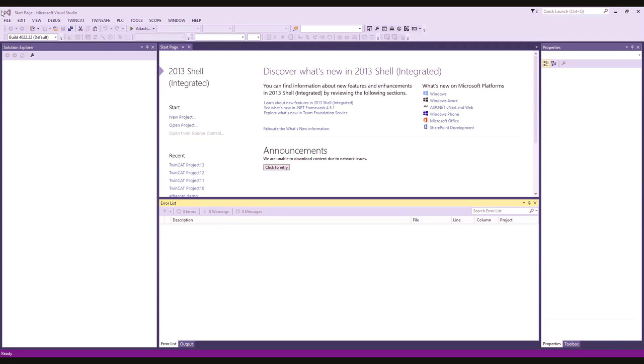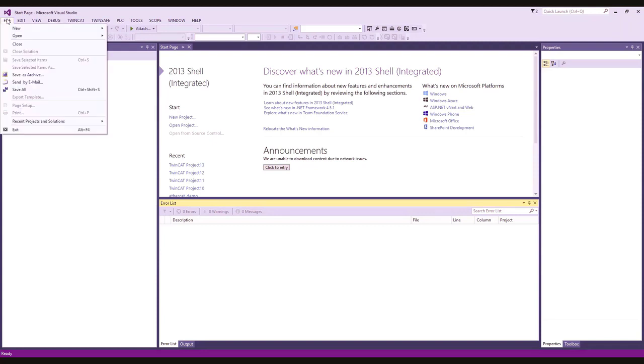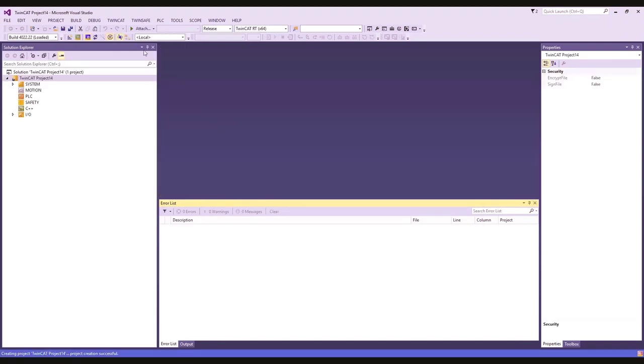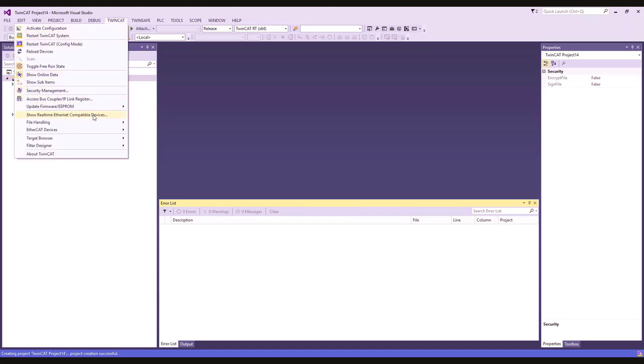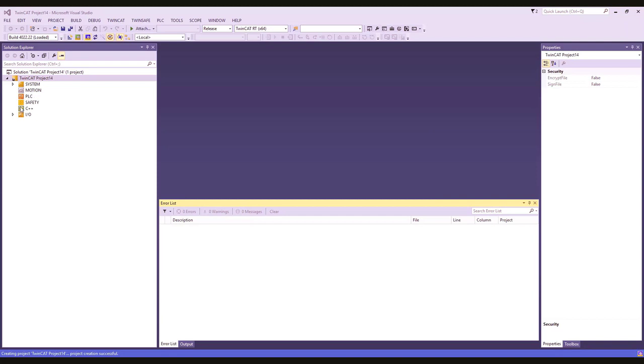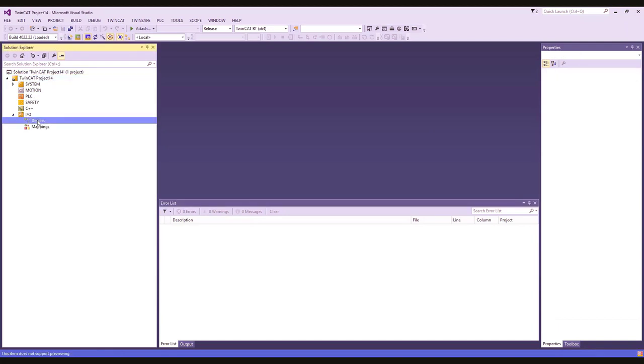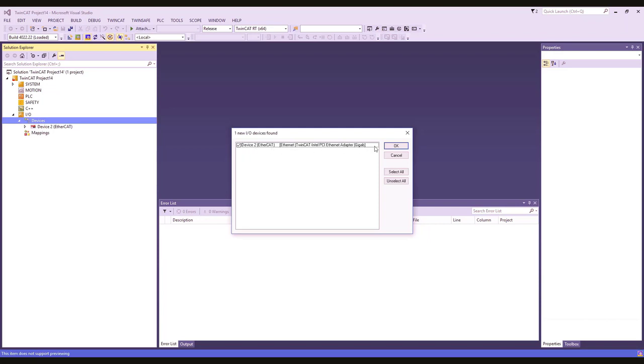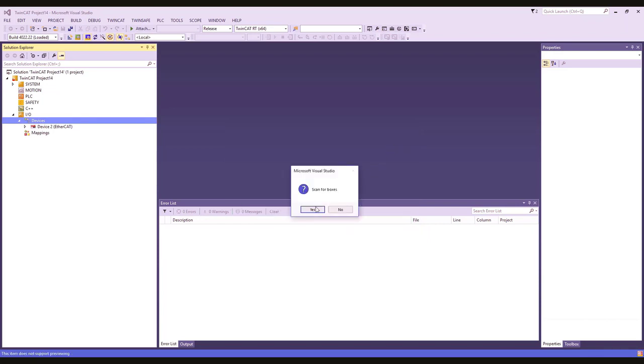After copying over the ESI file, open the TwinCAT application and create a new TwinCAT XAE project via the File > New > Project menu. Next, click TwinCAT > Show Real-Time Ethernet Compatible Devices, and then ensure that your Ethernet adapter is installed. After confirming installation, go to the IO tab, then click Devices. Right-click on Devices and choose Scan. After scanning for devices, click the checkbox next to the EtherCAT device, and then click Yes to scan for boxes.